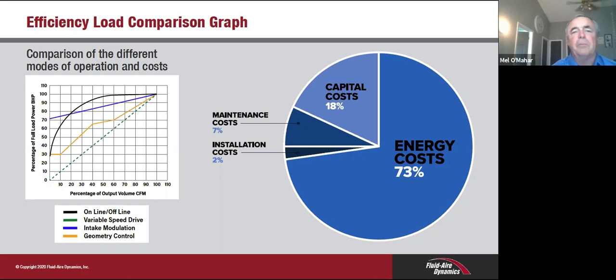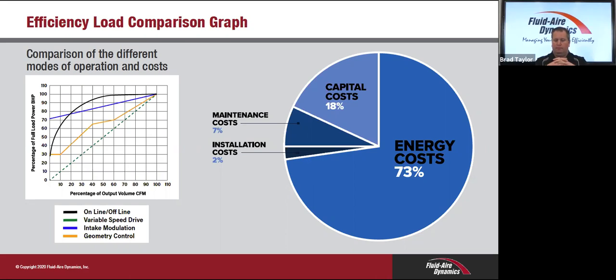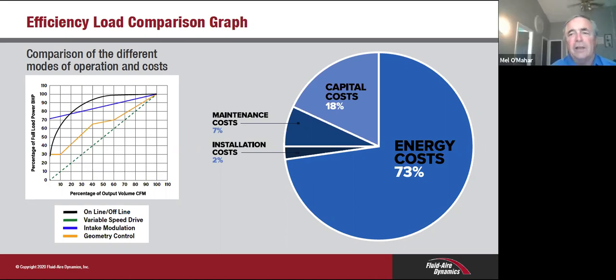And this becomes a real big issue with facilities that maybe have a scaled down second or third shift, where maybe the compressor is sized pretty well on first shift, but you get into second, third shift, and it's really just pulling a lot of power for you. So we go into every new customer by taking a look and data logging with them and seeing where we could save energy, because we all have to charge something for our equipment, but if we can save energy and be a good partner for you, that's what we're looking for.